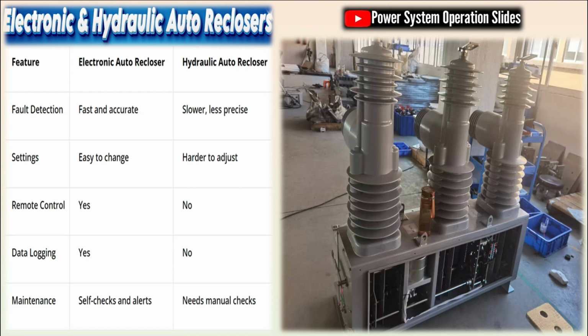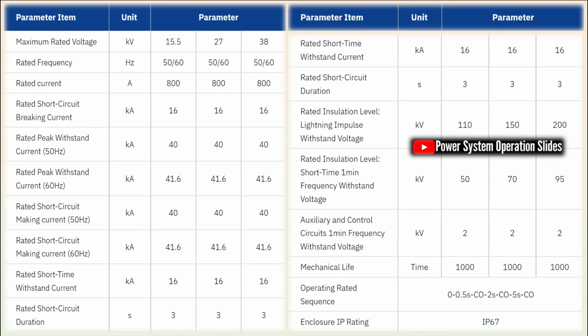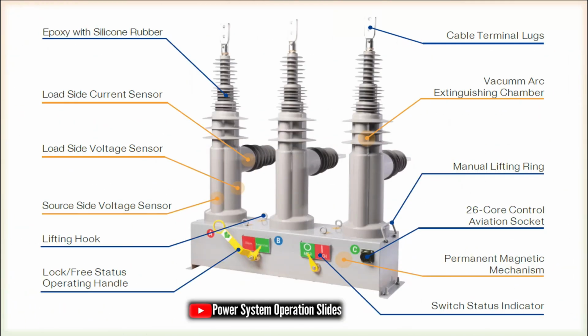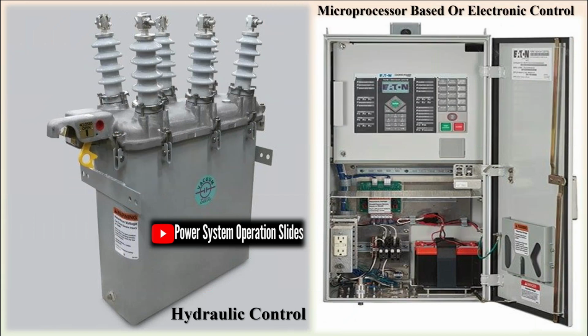2. Three-phase reclosers. These are used on three-phase circuits to improve system reliability and where lockout of all three phases is required for any permanent fault, to prevent single-phasing of three-phase loads such as large three-phase motors. The mode of operation is typically three-phase trip and three-phase lockout, where all contacts open simultaneously for each trip operation. The three phases are mechanically linked together for tripping and reclosing, operated by a common mechanism.